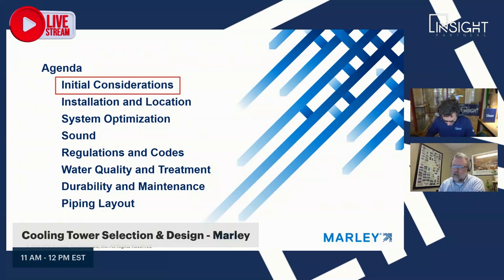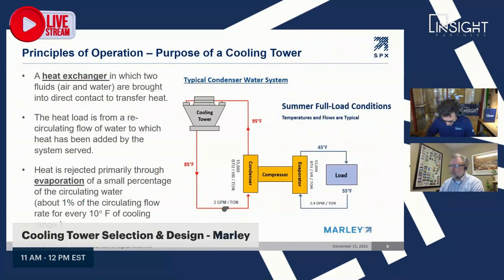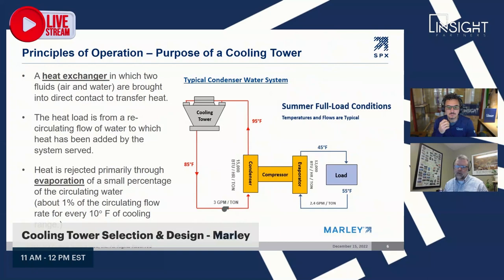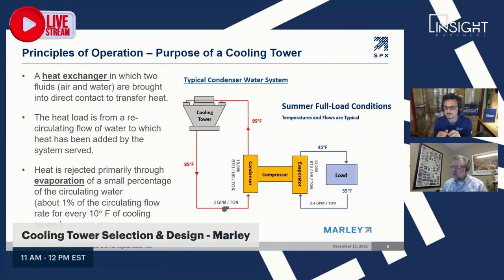Let's cover a little bit of fundamentals. What is a cooling tower? It is a heat exchanger — a unique one in that it's a direct heat exchanger where the two fluids are brought into direct contact with one another. We reject heat from the process primarily through evaporation. About 1% of the circulating flow rate is evaporated for every 10 degrees of range. We have a typical condenser water system where the building load gets sent out to the cooling tower and we reject that heat.